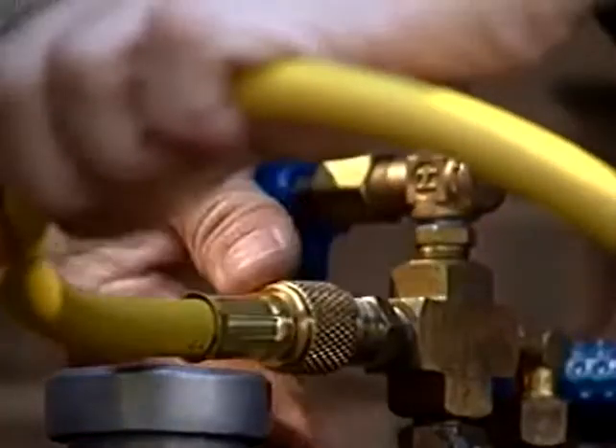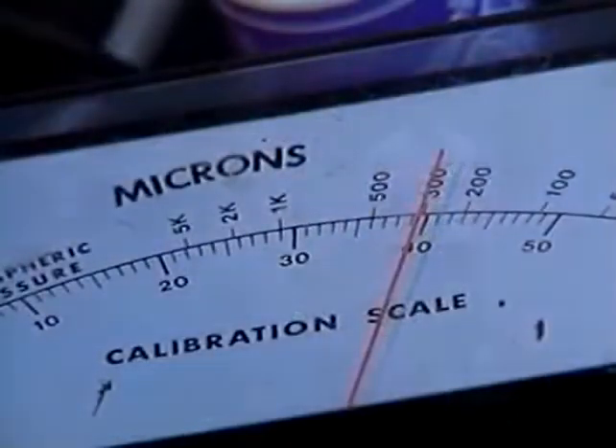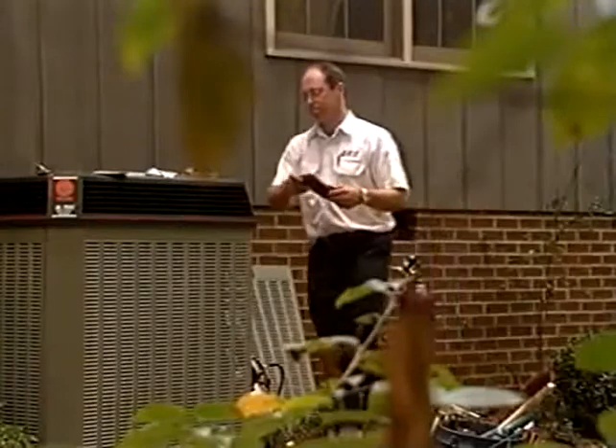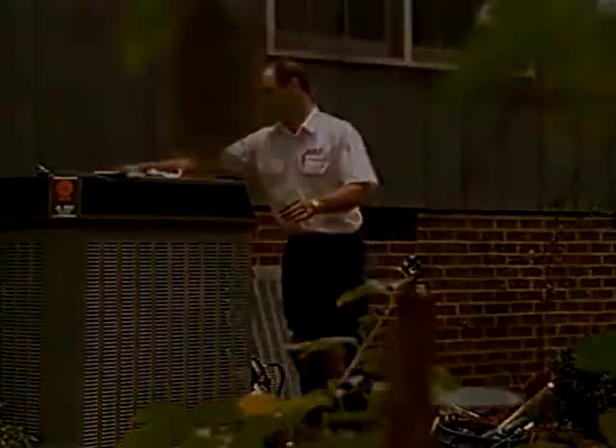But we know that there's significant differences in a vacuum that's being pulled at, let's say, 150 microns versus one at 500 or 750 or 800 microns. And many contractors don't even know whether their vacuum pump is even doing the job that it's supposed to. When pulling a vacuum, your micron gauge should reflect a reading of 500 or less. If not, you'll need to check the lines for a leak and repair it prior to charging.